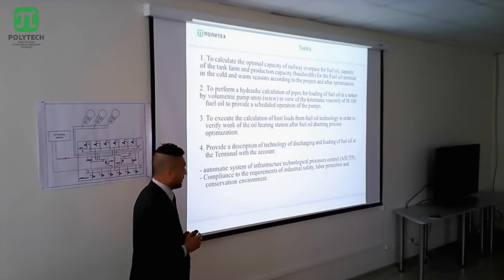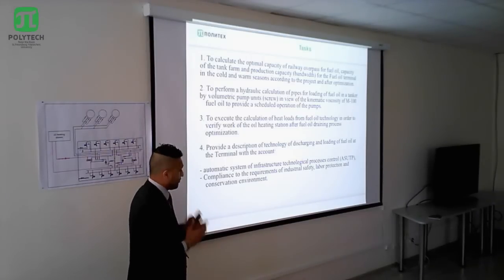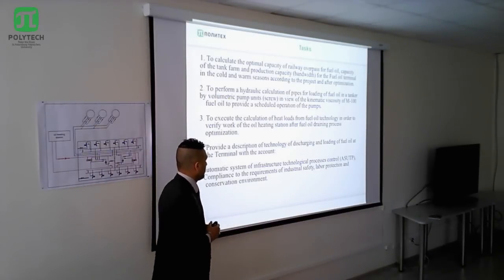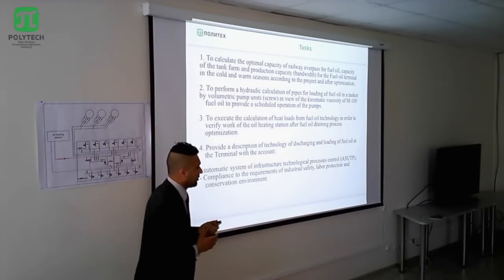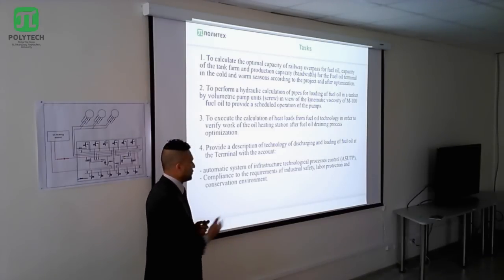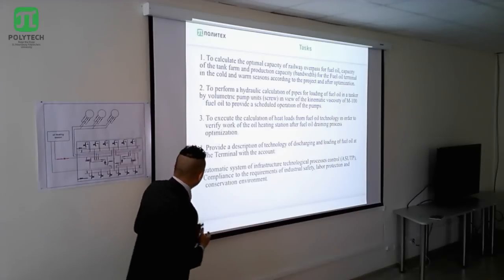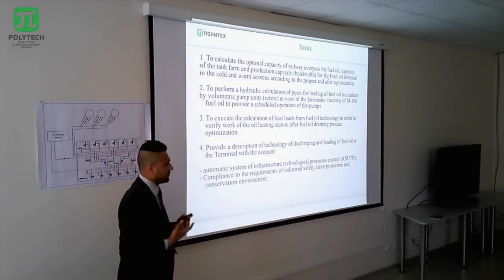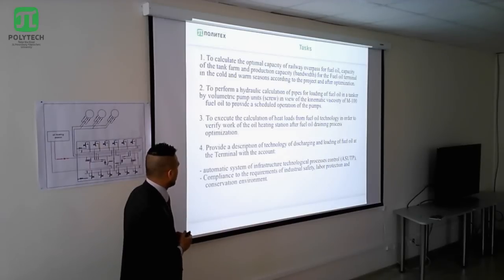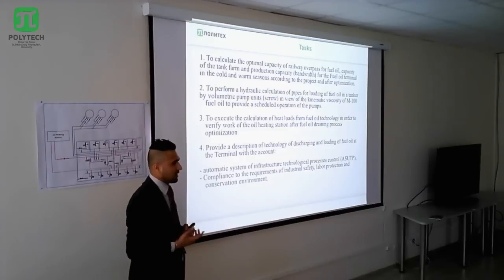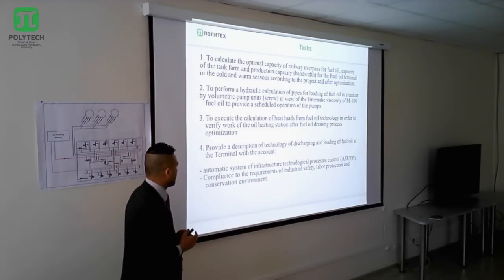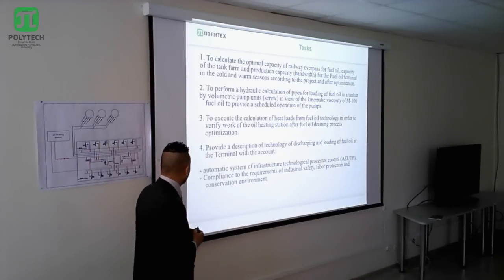After optimizing the fuel oil draining process, I performed a calculation of the pipes for loading fuel oil into a tanker using volumetric screw pumps, taking into account the kinematic viscosity of M100 fuel oil, to provide a schedule of pump operation. Finally, I provided a description of the technology for discharging and loading fuel oil at the terminal, taking into account the automatic system for infrastructure and technological process control, and compliance with requirements for industrial safety, labor protection, and environmental conservation.